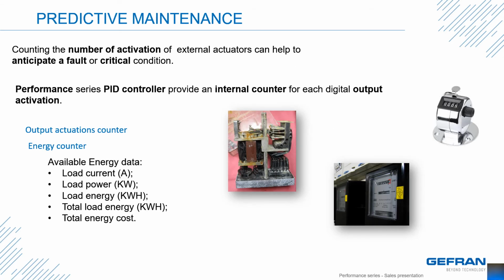Predictive maintenance. The performance series can give you feedback on output actuations, so you can approximate machine needs, schedule maintenance, or replacement on the outputs of the controller. There's also an energy counter giving you load current, load power, load energy, total load energy, and total energy cost. All of this information is available from the front panel or through digital communications to the unit.